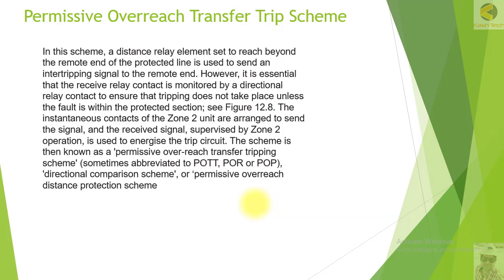In this scheme, a distance relay element set to reach beyond the remote end of the protected line is used to send an inter-tripping signal to the remote end. However, it is essential that the received relay contact is monitored by a directional relay contact to ensure tripping does not take place unless the fault is within the protected zone. The instantaneous contacts of the zone 2 unit are arranged to send the signal, and the received signal supervised by zone 2 operation is used to energize the trip circuit. The scheme is known as the permissive overreach transfer tripping scheme, sometimes abbreviated as POTT, POR, or POP direction comparison scheme.